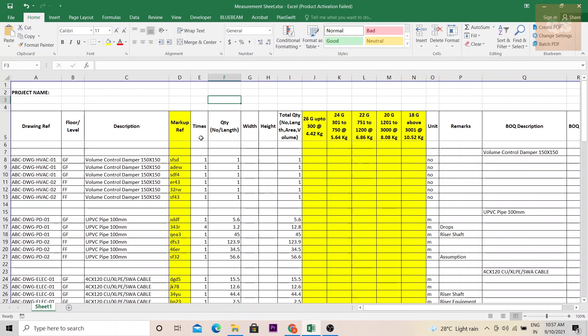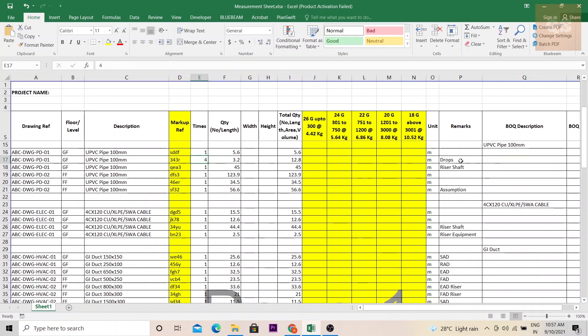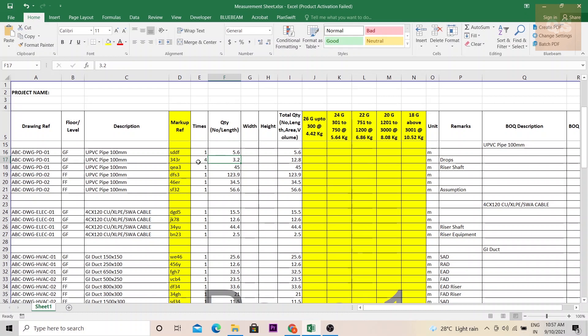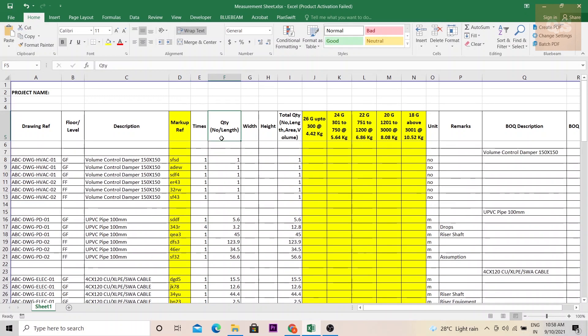Then you have the next column called times. Times is just giving you the number of times the particular item needs to be calculated. Sometimes if you see here this pipe I have mentioned as four. Sometimes there might be some drops which will not be shown in the plan. Imagine there are some four number of toilets in ground floor. In this drawing there are four toilets and the length of that drop is 3.2 meters. So instead of just measuring each separately we can just mention four and multiply that length and you can get the total length here. This column is the product of this times and the quantity.